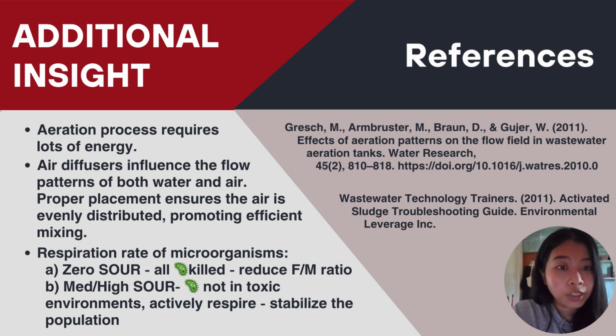Effective respiration means effective degradation of the pollutants. When the SOUR value is zero, it indicates the inactivation of the microorganisms, or the possibility that the microorganisms in the activated sludge have been killed.